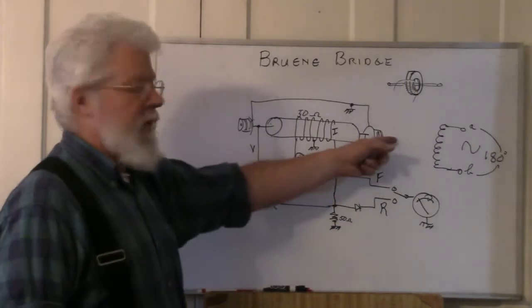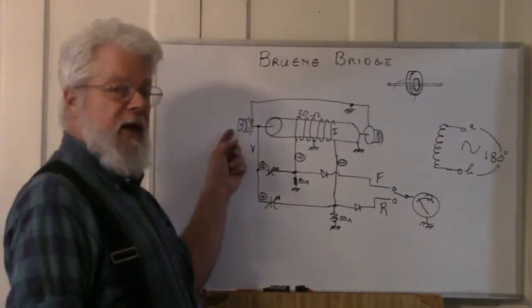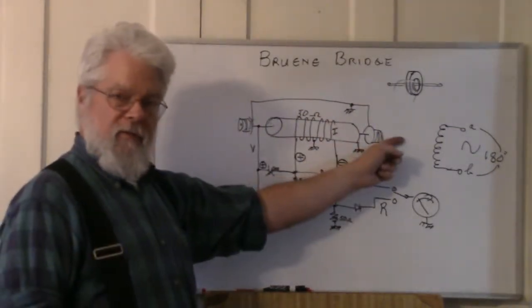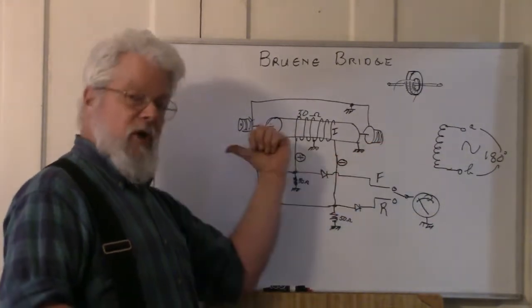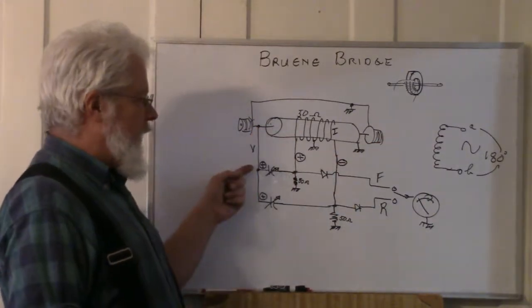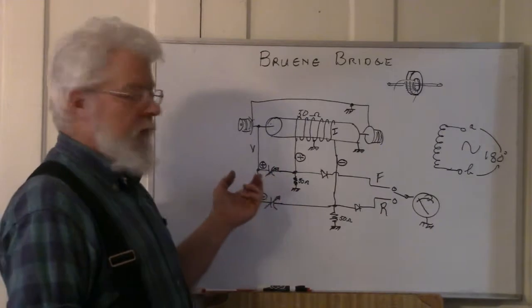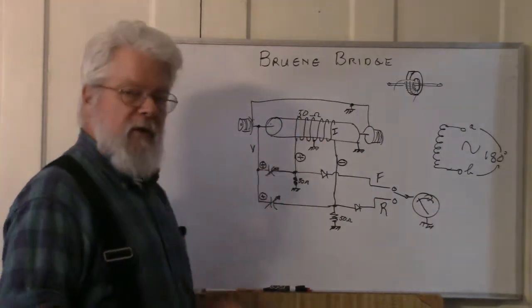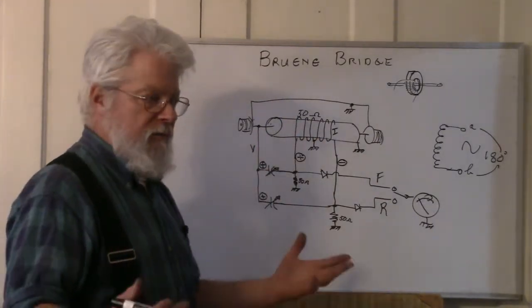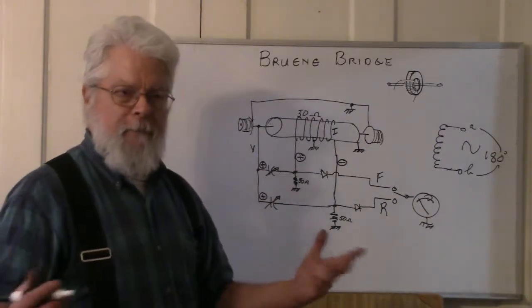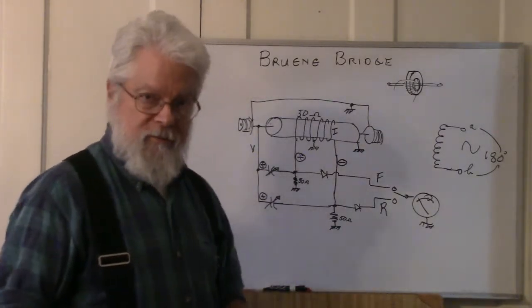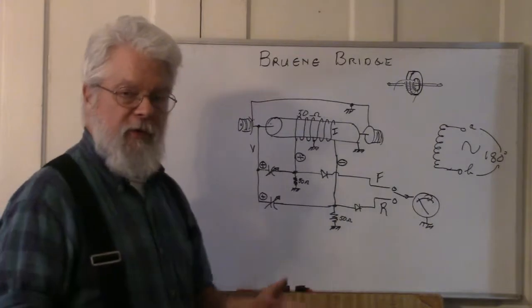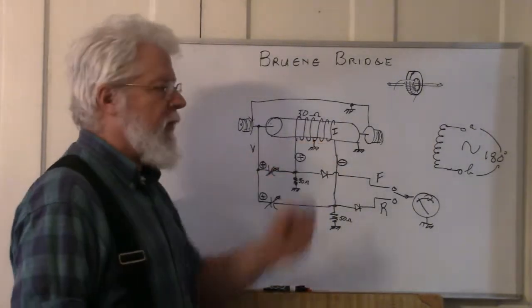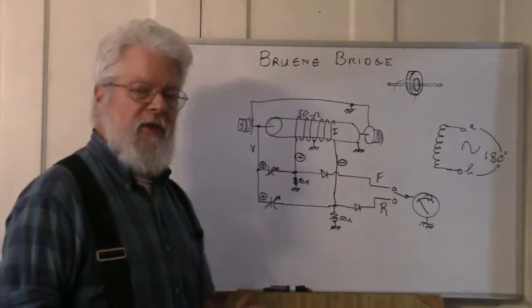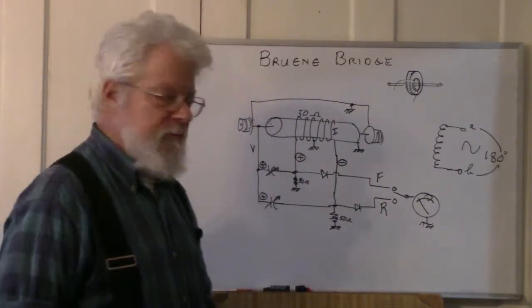And then you take your matched load and you put it on the opposite end, put your transmitter on the load end, and go the other way and adjust this for zero. So now both forward and reflected are not calibrated, but they're balanced. You balance them out for zero. So the voltage and the current for a 50 ohm matched line condition cancel out to zero.